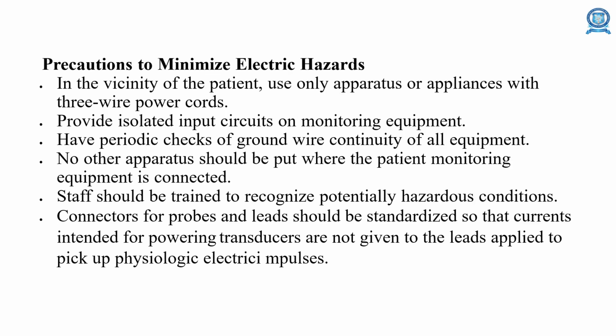Precautions to minimize electric hazards: in the vicinity of the patient, use only apparatus with three-wire power cords, and have periodic checks of ground wire continuity. Staff should be trained to recognize potentially hazardous conditions. Connectors for probes and leads should be standardized so that the currents intended for powering transducers are not given to the leads applied to pick up physiological electric impulses.